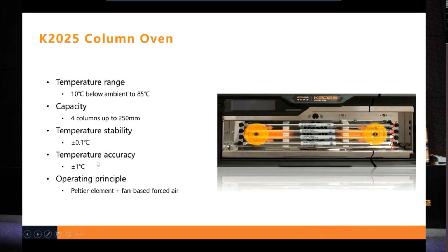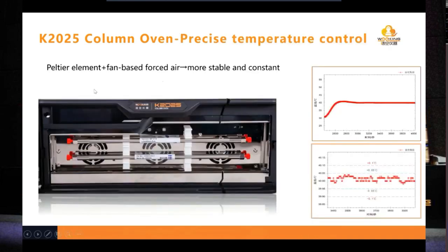And the operating principle of the oven is based on Peltier element and fan-based forced air. This is the inside of the column oven. The two combined temperature control principles can ensure the temperature is more stable and constant. The fluctuations of the temperature are within 0.05 Celsius degree. This is the zoom picture of the front.